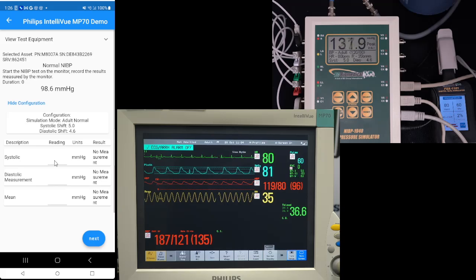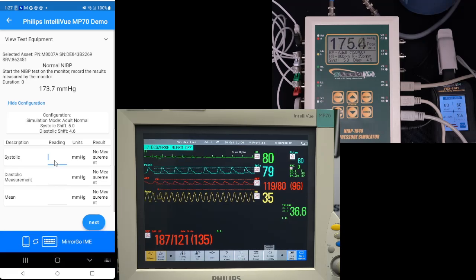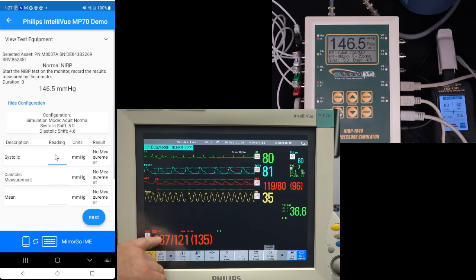And we can see on the screen here, it's showing the pressure that's reading. That's live from the NIBP itself. So as it runs here, it'll get a measurement. Now the NIBP doesn't have any connection to the monitor itself, so there's no way for it to get these measurements from the monitor. So I do have to enter these numbers manually, just because there's no way to automatically read that.